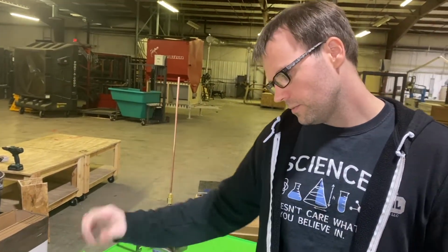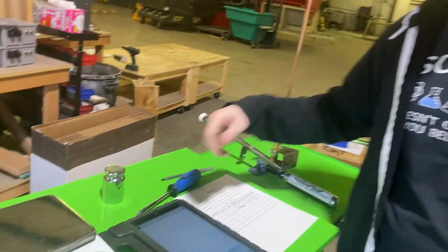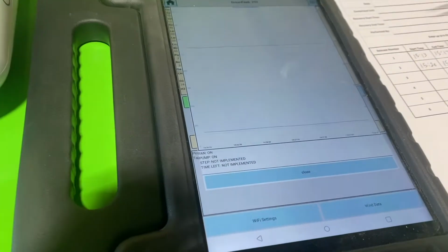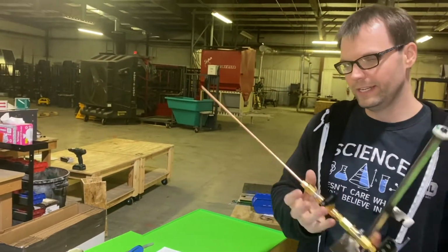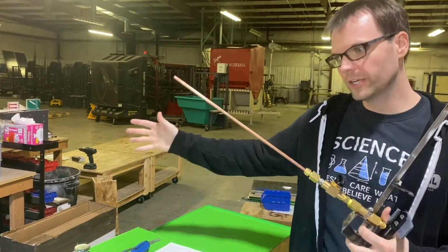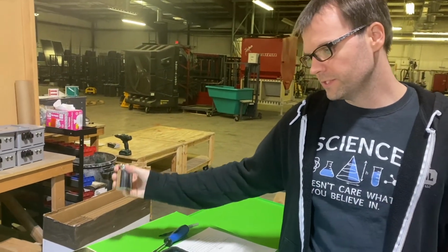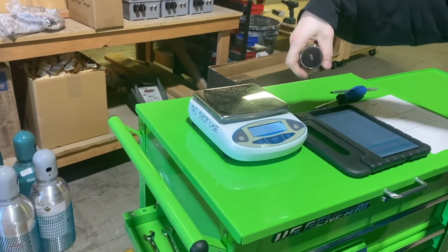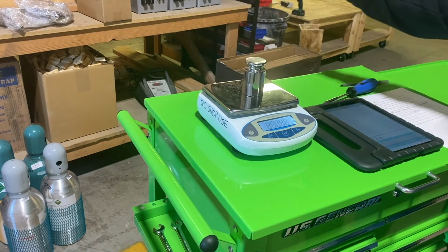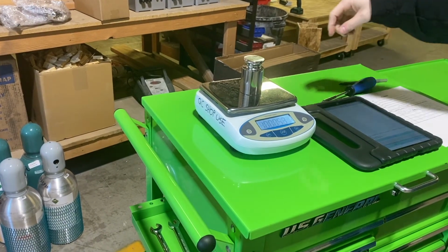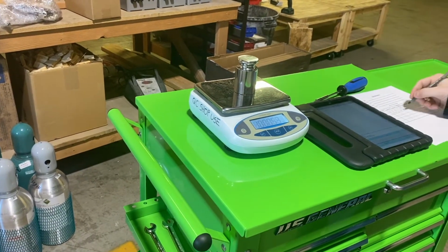All right, the 3 minutes is up, and the system is ready for another CO2 release. So first we need to weigh our system and make sure there's no condensation or ice that's formed on it. And it's still cold, but we'll just go a little bit longer to compensate for that. First we're going to make sure that our scale is reading 0, put our calibration weight on it, and we're still reading the same number. I'm going to write that number down.